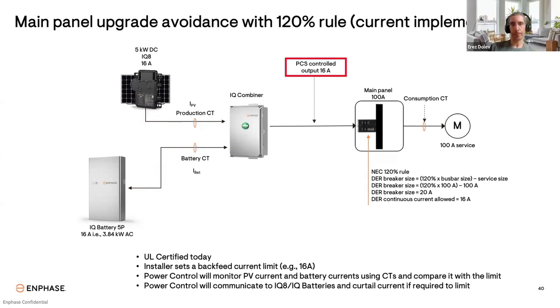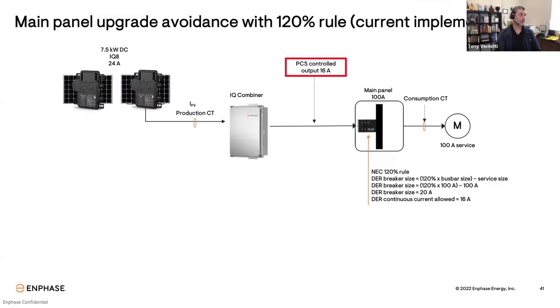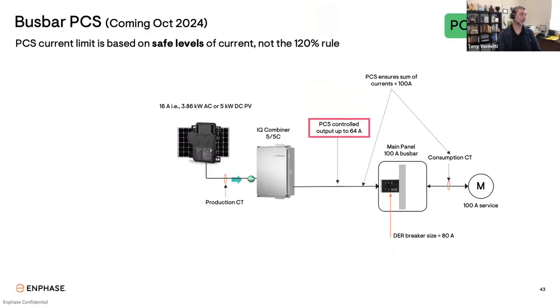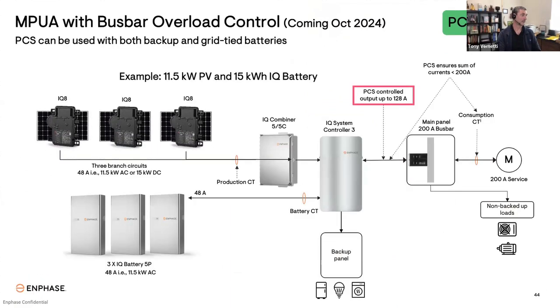He's saying yes. Okay, so here I've got the diagram up of Busbar PCS with storage. There are 3 CTs needed for PCS, and they all come with the Combiner 5. Those are 2 consumption CTs on the main feeders to the main panel, a production CT, which is inside the IQ Combiner 5, and a battery CT, which is included with the combiner and has to be installed on L2 of all of the batteries in the system. With those 3 measurements, we can do any of the versions of PCS that we mentioned.